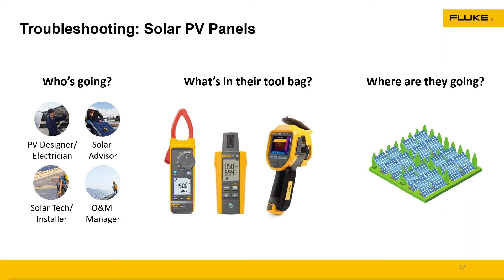But what happens if the output voltage and current go down? Sometimes one panel may go down, or the whole line goes down, and this is where they start tracing out the system, either looking through a thermal imager or using a DMM to check where the voltage output would be. Typically the technician goes to the combiner box, since everything ties in there, and they can do voltage and current checks from that point.